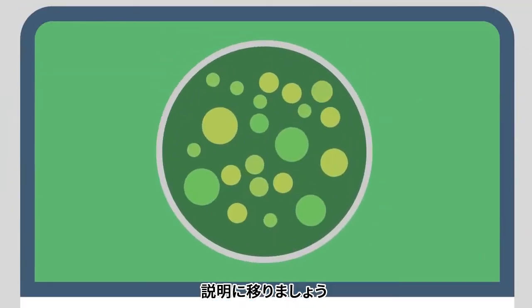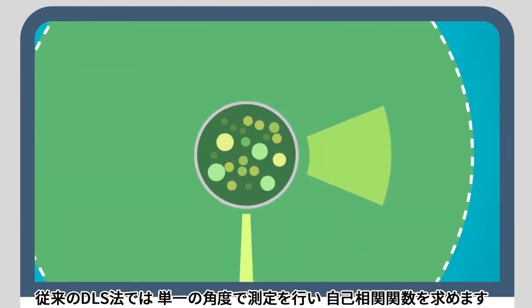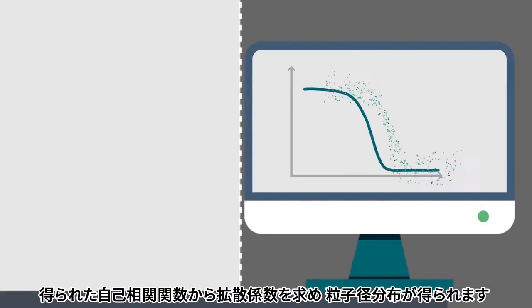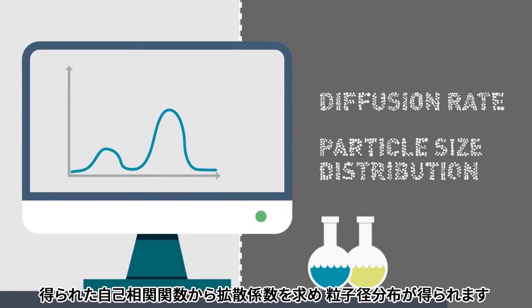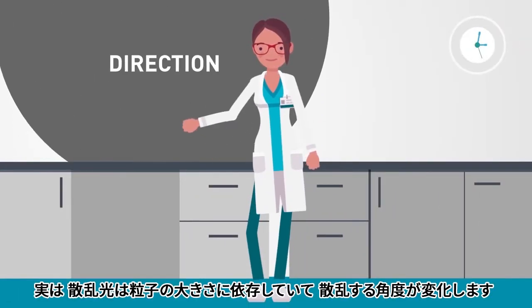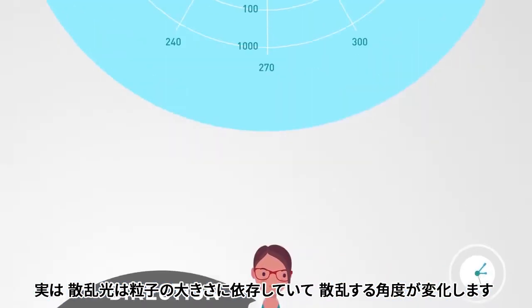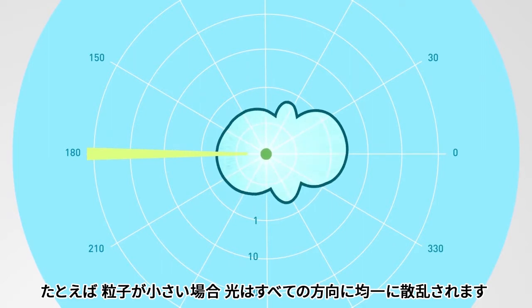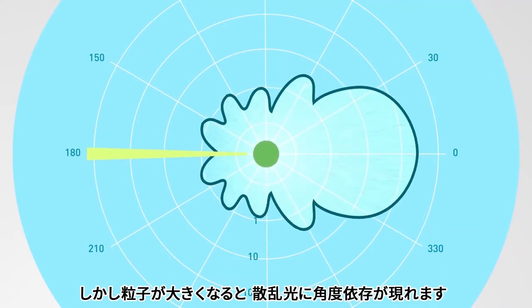With traditional DLS experiments, the scattered light is detected at a single angle and auto-correlated to determine the correlation function. The correlation function is used to calculate the diffusion rate of the particles, from which the particle size distribution is obtained. What's interesting is that the direction and the number of photons scattered depends on the size of the particle. For example, if the particle is small, light is scattered quite uniformly in all directions. However, if the particle is large, more light is scattered in the forward direction.